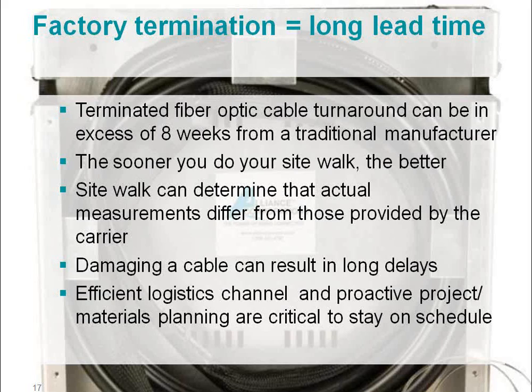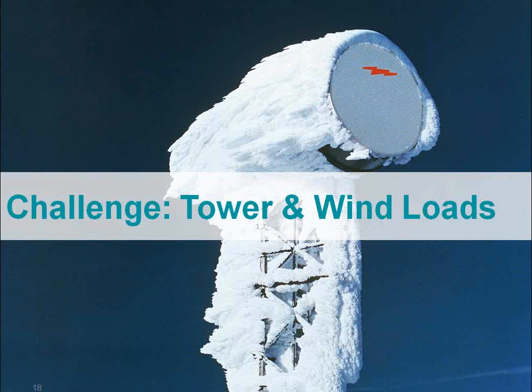So it's very necessary to plan before the site installation begins. This will keep costs in line. It prevents downtime, delays and scrap. Now, there are always exceptions, and we understand that there are unexpected issues. Just know that if you have an issue with a cable, if it's too short or too long, you have other options rather than starting from scratch.